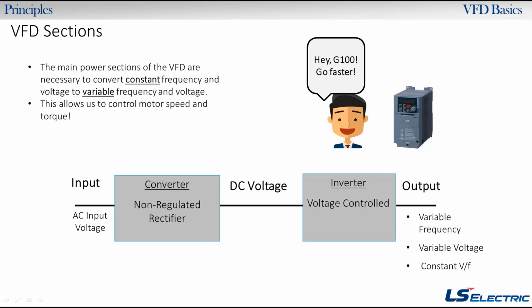So we have an input. This is where you're going to have your single phase or three phase input voltage. Then you're going to have a converter, which is going to convert the AC into a DC voltage. Okay, we'll have some capacitors here. We'll show you that. And that DC voltage gets inverted, gets chopped up into kind of like a pseudo AC waveform, which we call a PWM. And with that waveform, we're able to convert this constant voltage source into a variable frequency, a variable voltage, and then we could have a constant V by F pattern. We could have a variable one, we could have a custom one, we could have a derated one. There's lots of things we could do with the output voltage. It's fully customizable. So that's one of the benefits of running a VFD.